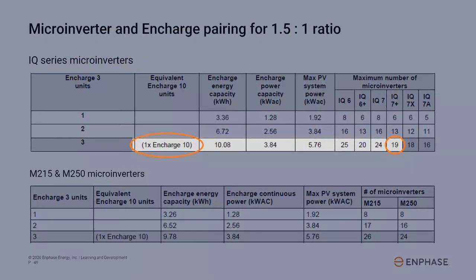Just as an example of the limitations with that 1.5 to 1 ratio, with a single Encharge 10 installed, normally the maximum number of IQ7 plus microinverters that you could install would be 19. So again, with solar circuit control, you can go well above 19 as long as it's configured so that portion of that solar array is turned off, so that when they're disconnected from the grid, only 19 of the IQ7 pluses are active.